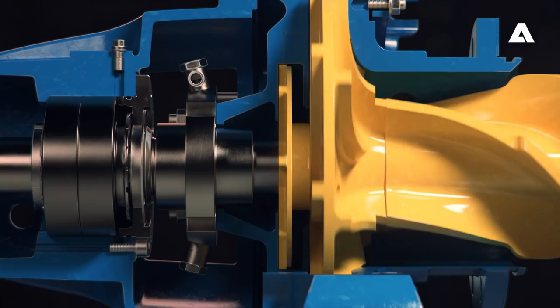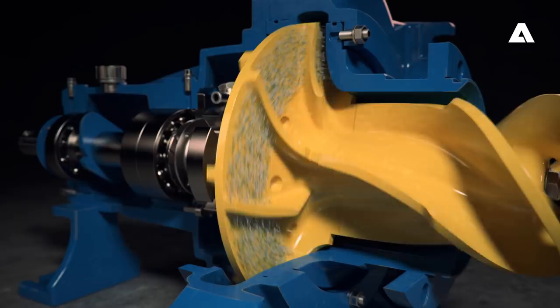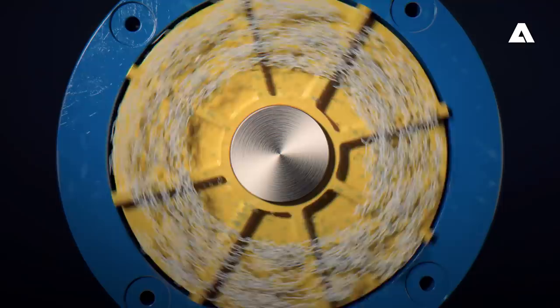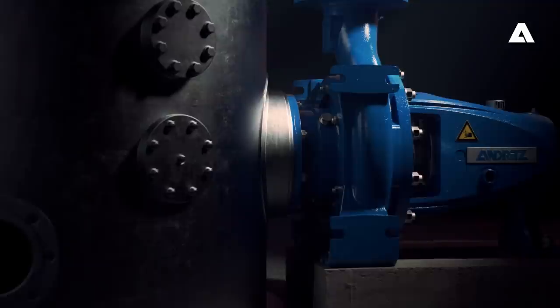Installed behind the impeller, it allows gas to flow and prevents the medium from escaping, while the air is fed into the degassing chamber. This occurs only by centrifugal forces and results from the design and arrangement of the components. There is no resistance for the outflowing air, and loss of medium during the continuous degassing process is excluded at any operating situation.